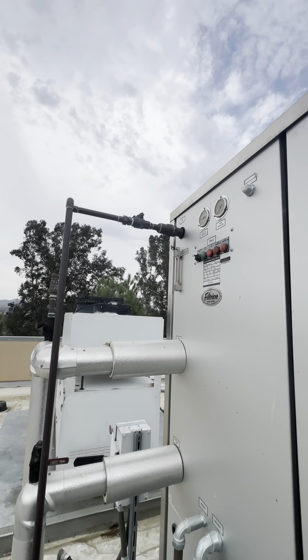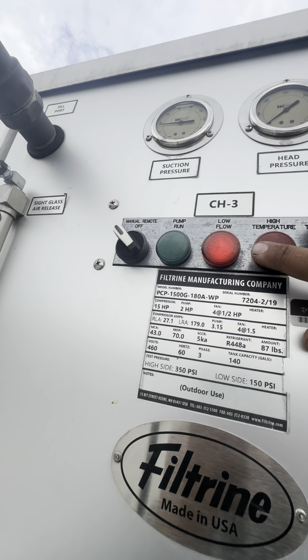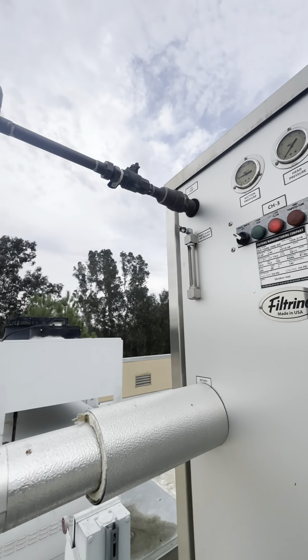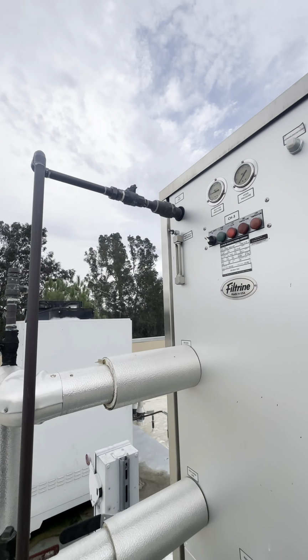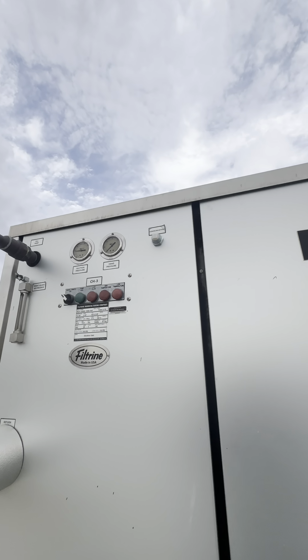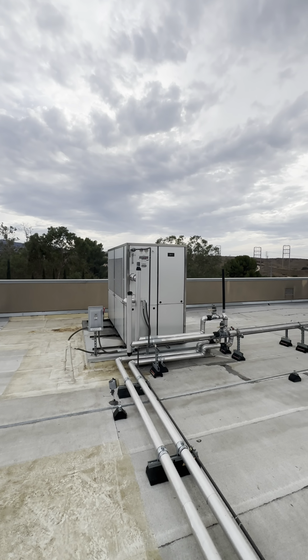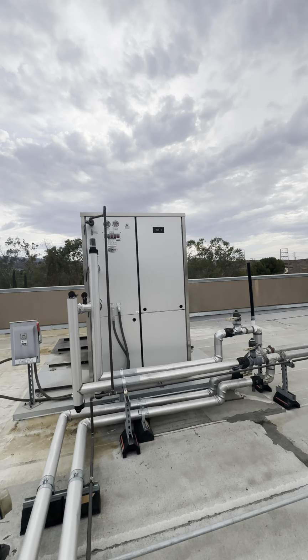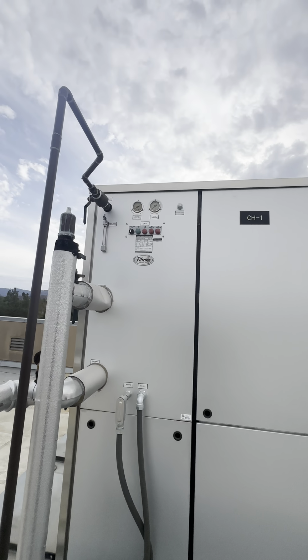So real quick, we see on chiller number 3 we have a low flow issue. We're going to have to put some gauges on the water lines just to verify that we do have some water pressure in here. But I'm going to take you along through this service call. They just want one of these up and running for their MRIs.